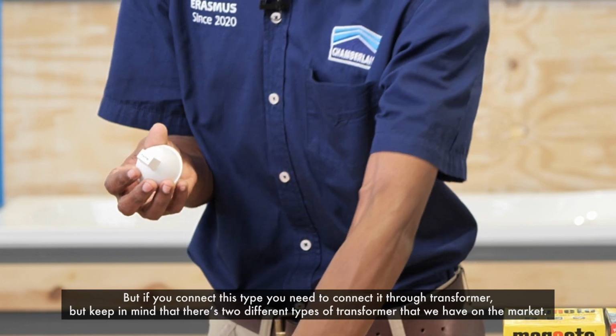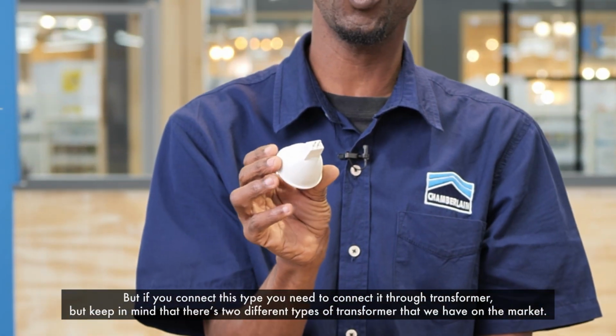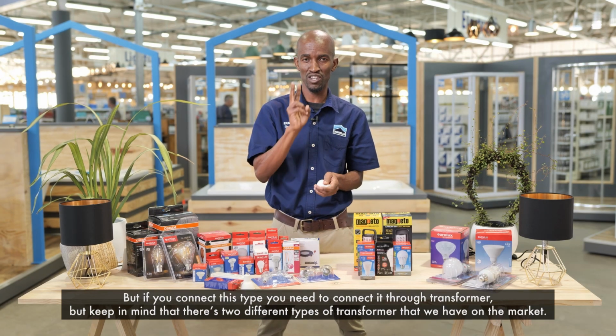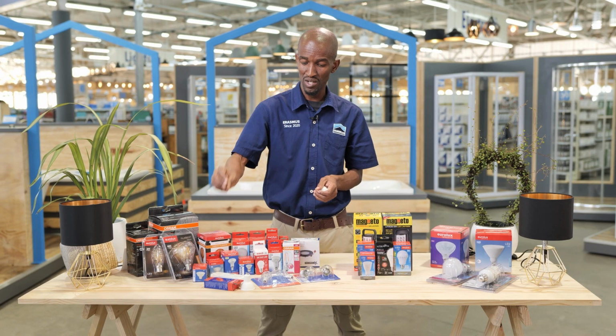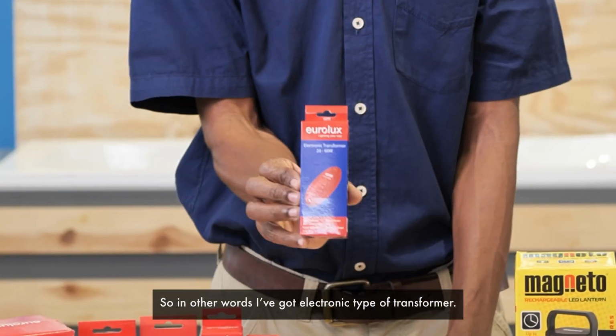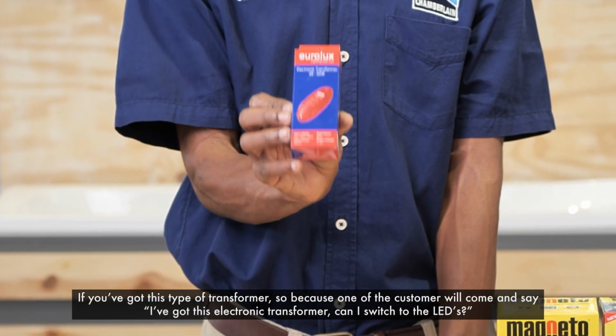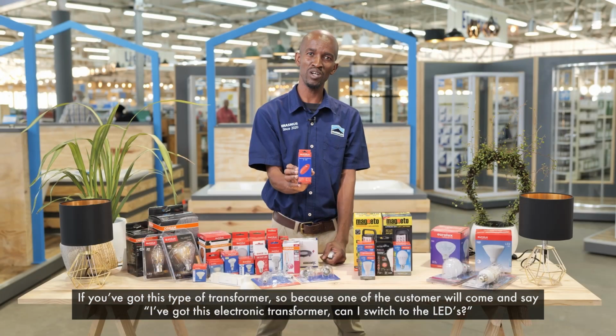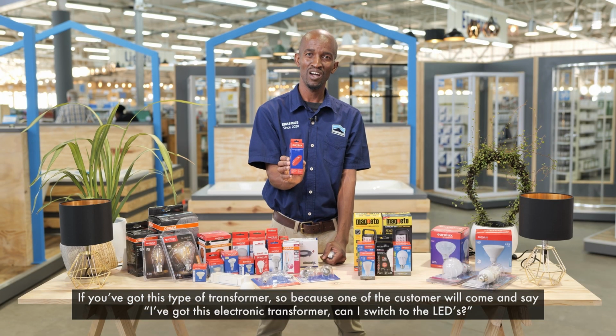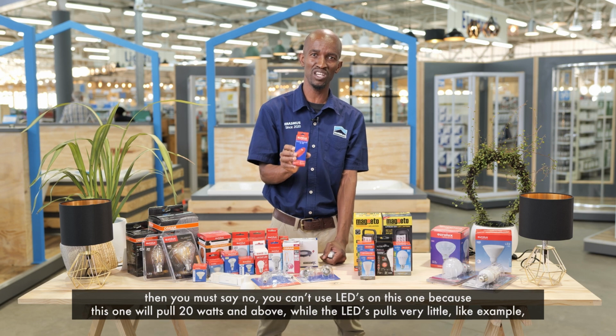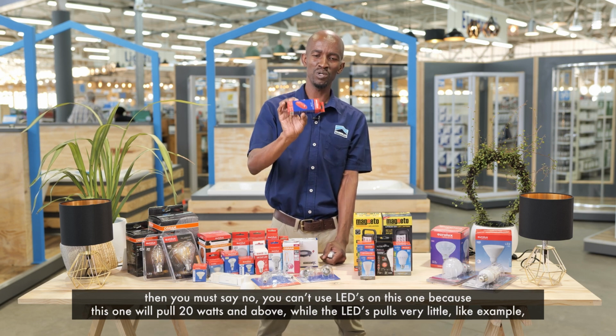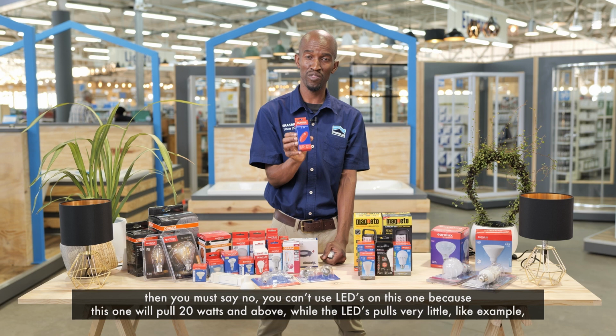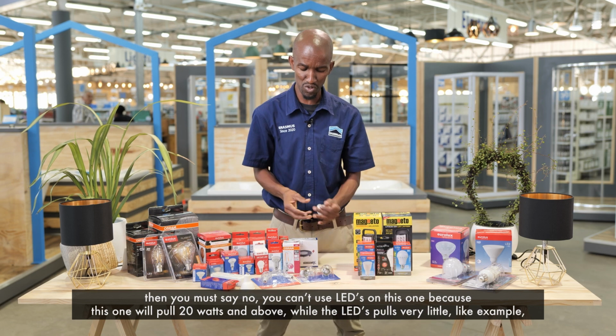But if you connect this type, you need to connect it through a transformer. Keep in mind that there are two different types of transformer on the market. I've got the electronic type of transformer. One of the customers will come and say, I've got this electronic transformer, can I switch to LEDs? Then you must say, no, you can't use LEDs on this one, because this one will pull 20 watt and above, while LEDs pull very little.